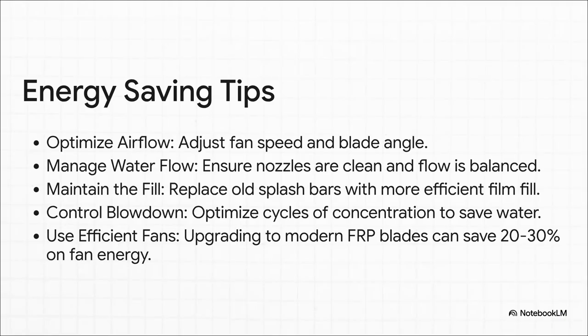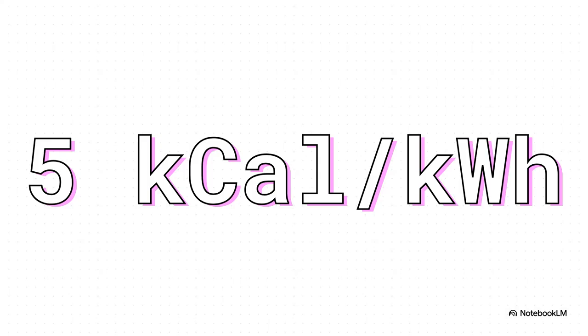Keeping these towers running at peak performance is a constant battle. The opportunities for saving energy are just massive. It comes down to a few key things: tuning the airflow, managing the water flow by keeping everything clean and balanced, and carefully controlling the water chemistry. A single upgrade, like switching to modern fan blades, can cut the energy for the fan by up to 30%.